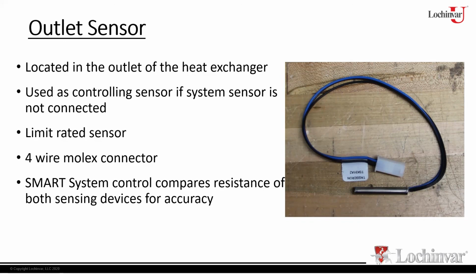Now, if one of those was reading, let's say one was reading 180 and the other thermistor was reading 90, okay, the control module is going to go, which one of these is right? I don't know, right? Because one reads this, the other reads that. I don't know which one of these is correct. So if I don't know which one's correct, I can't trust what the sensor's telling me. So that means I can't use it.